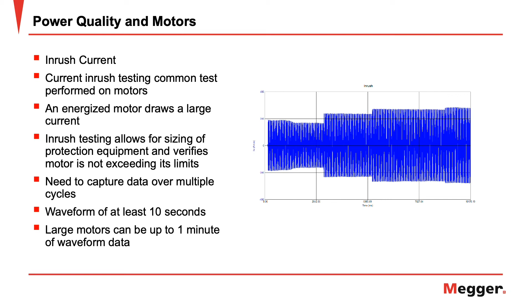Now, in order to adequately view inrush data, you need to be able to view the data over multiple cycles until the inrush is stable. In order to do this, a waveform of at least 10 seconds should be captured. And for very large motors, it may be needed to capture waveforms for up to 1 minute.